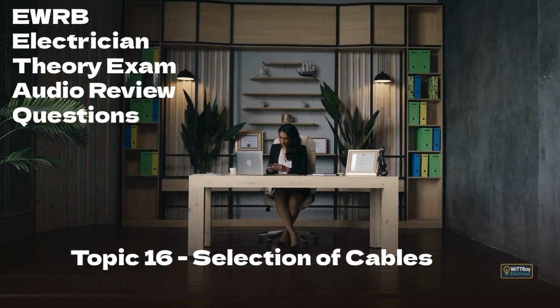A cable may be thermally fine but still drop too much voltage over a long run. That can cause dim lights, motor starting issues, nuisance tripping, or equipment not operating within design limits. Review question 28. What is one likely result of excessive voltage drop on a motor circuit?